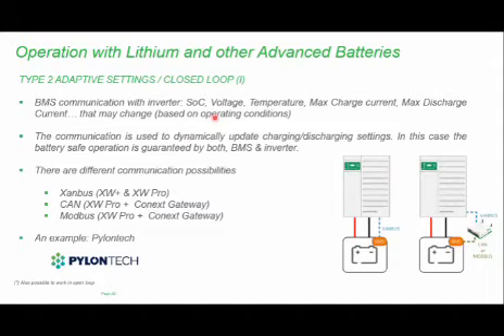So things like state of charge, voltage, temperature, everything that the BMS of the battery feels and tells the inverter, 'okay, this is how I want you to operate,' it does perfectly well. Even another key advantage of closed loop communication is that it saves time on configuration of your system during initial commissioning. Because when it comes to voltages, charging, and all of these features that you'd otherwise have to input directly, the BMS actively speaks that to the inverter, so you do not have to bother about that aspect.